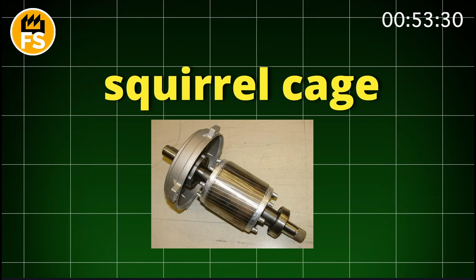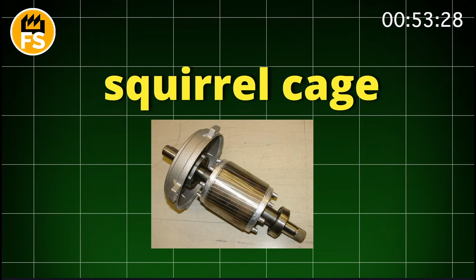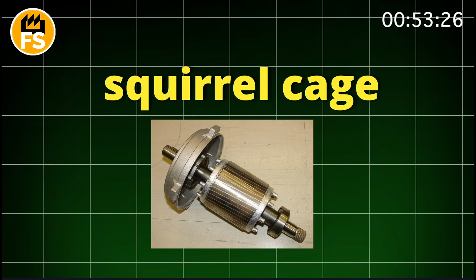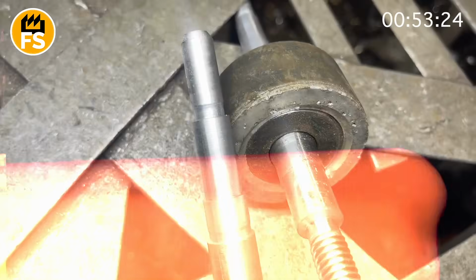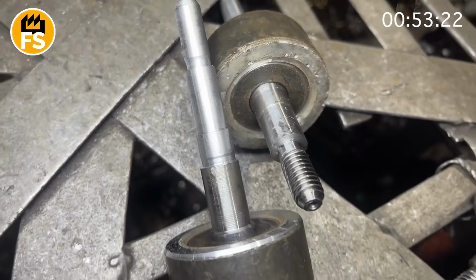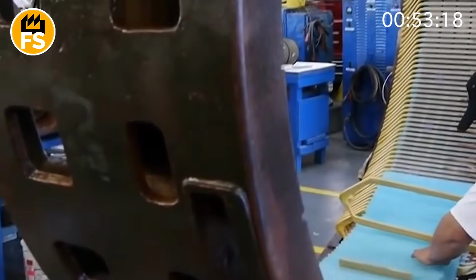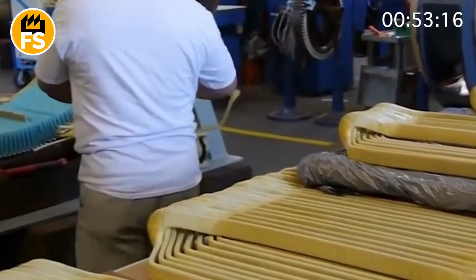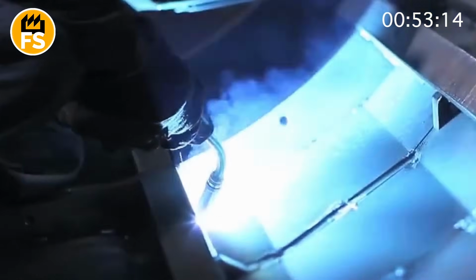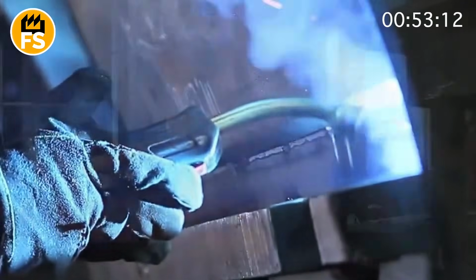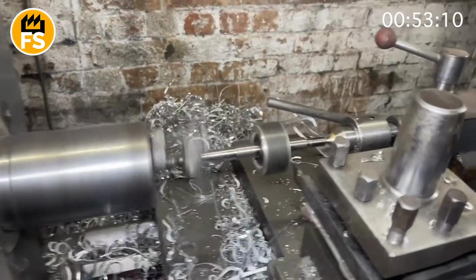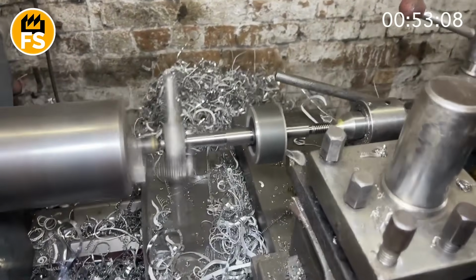One of the most common options is the squirrel cage. Aluminum or copper bars are inserted into the slots, and both ends are cast into rings, like a hoop around a cage. This creates a closed current loop. Such a design doesn't need to be connected directly. Current is induced inside automatically as soon as the motor starts. It's a simple, reliable, and mass-produced option for industry.